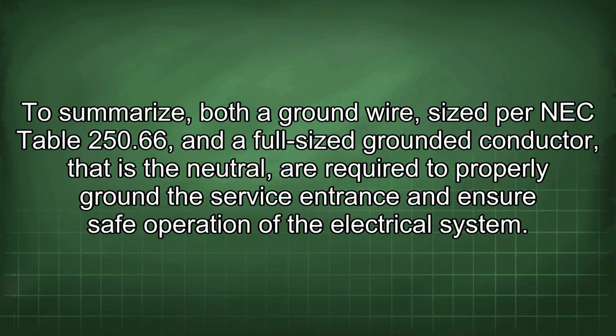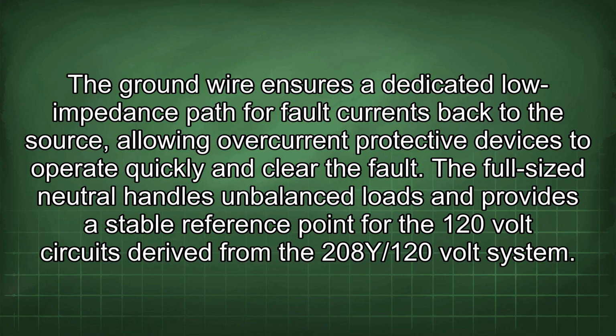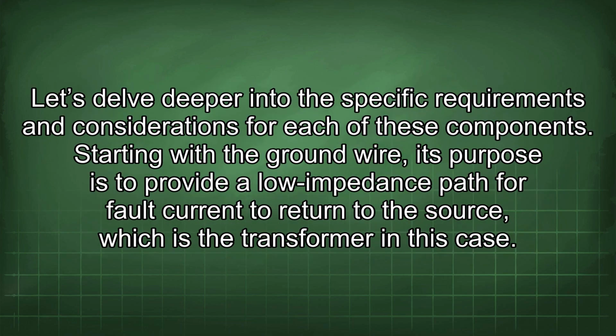To summarize, both the ground wire, sized per NEC Table 250.66, and a full-size grounded conductor, that is the neutral, are required to properly ground the service entrance and ensure safe operation of the electrical system. The ground wire ensures a dedicated low-impedance path for fault currents back to the source, allowing overcurrent protective devices to operate quickly and clear the fault. The full-sized neutral handles unbalanced loads and provides a stable reference point for the 120-volt circuits derived from the 208Y/120-volt system. Let's delve deeper into the specific requirements and considerations for each of these components.